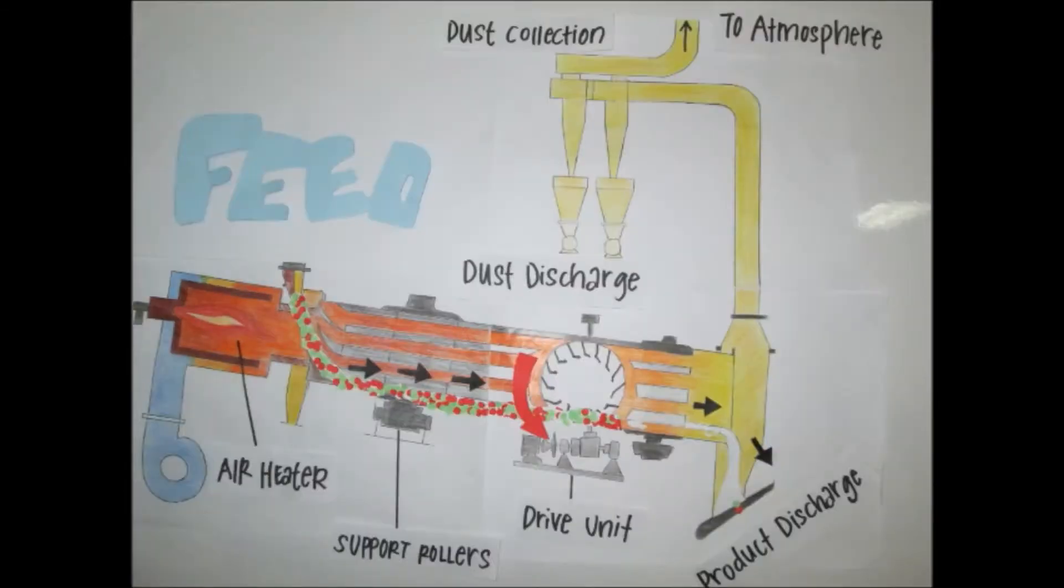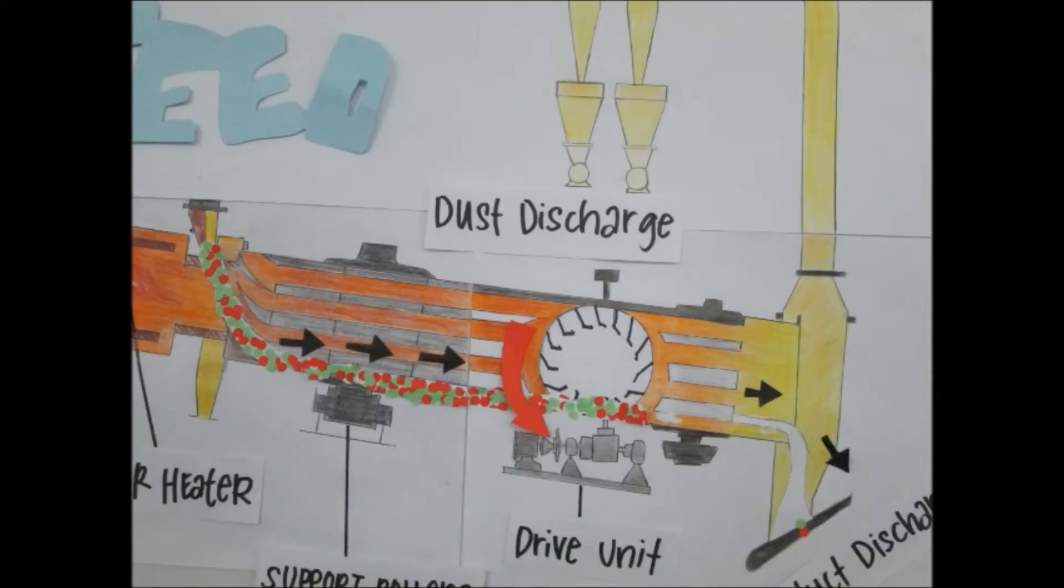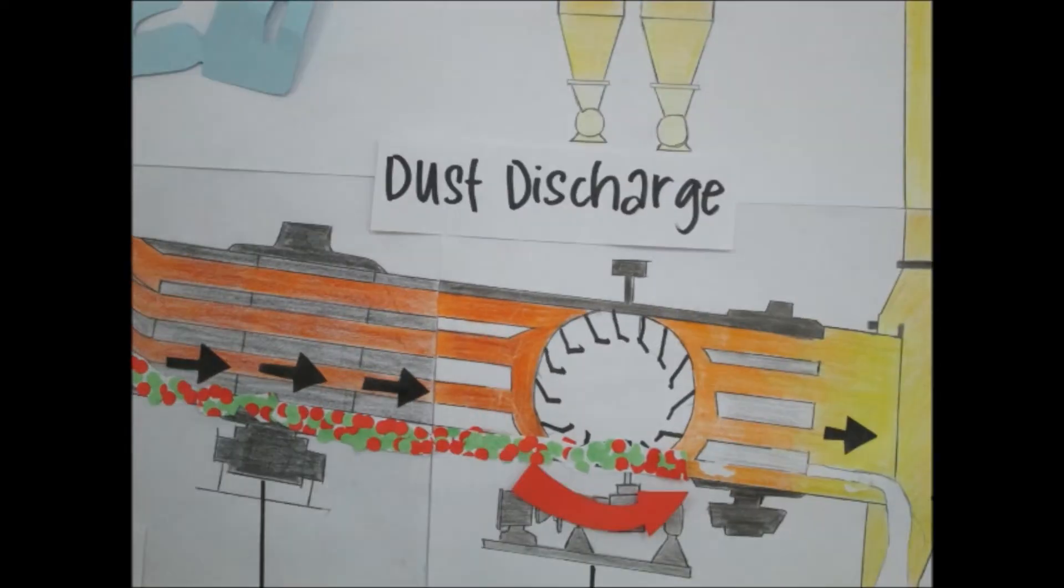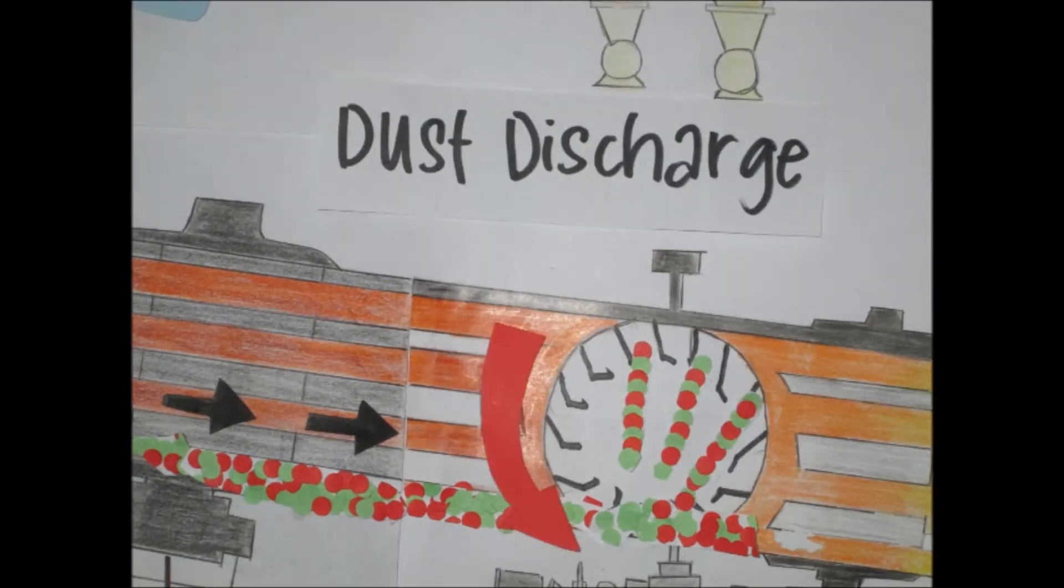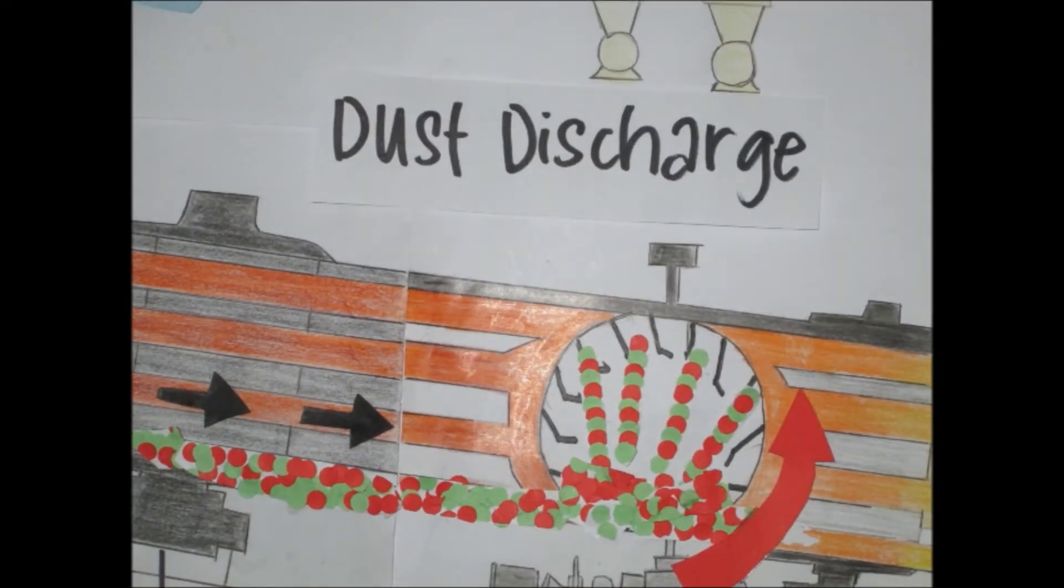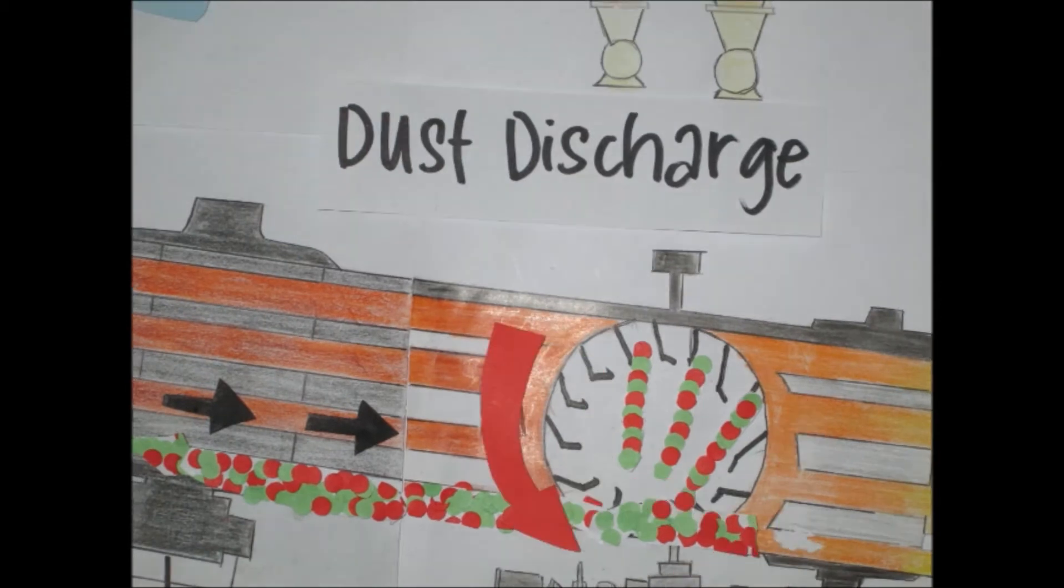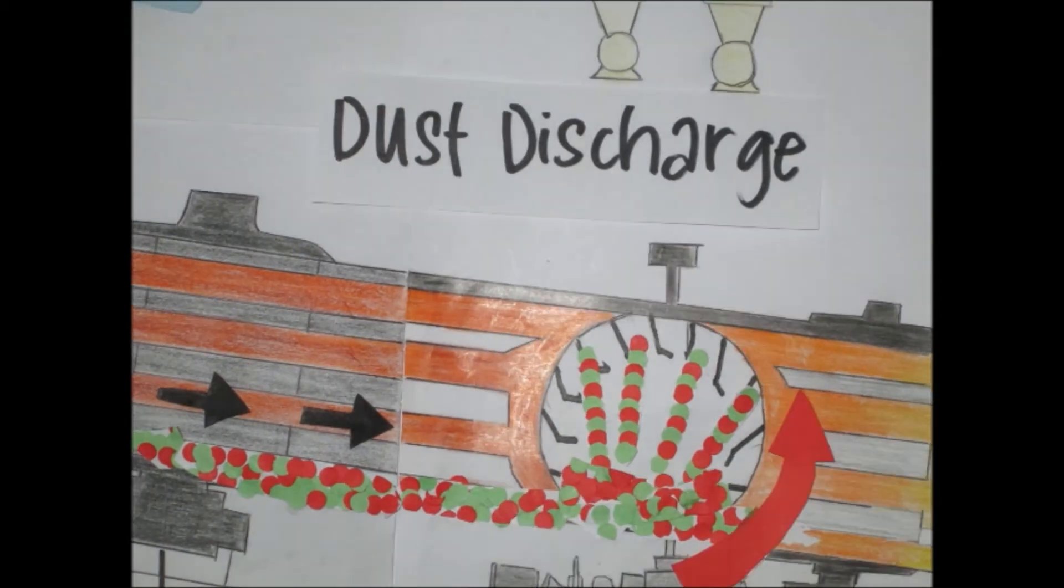The wet material is in contact with the gas at its highest temperature, which rapidly evaporates surface moisture. The initial heat transfer rate is high, causing an immediate and considerable drop in gas temperature, which prevents overheating of the material in the dryer shell.